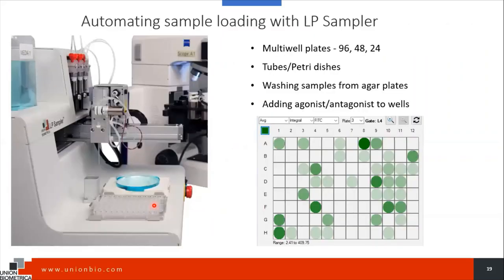We also have different automation tools that can work with our flow cytometer. By default all our flow cytometers can sort into tubes or multiwell plates such as 96 or 384, and can sort to petri dishes. You could also use it as an analysis tool — bring your cell clusters in a tube, set your plates with the flow cytometer, add your drug, incubate, and then use the LP sampler to sample from the wells, send back through the flow cytometer for reanalysis, and potentially resort back into the same plate.